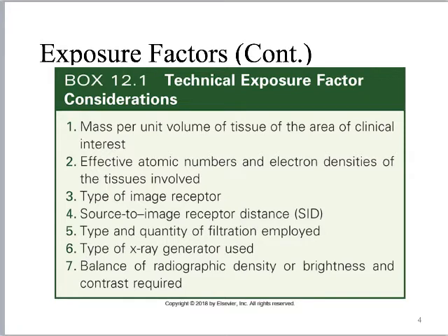There's also compensating filtration — things like a wedge-shaped filter sometimes used for feet examinations — which can also decrease patient dose. Regarding the type of generator used: older x-ray rooms with generators that fluctuated in power supply caused fluctuation in photon energy, increasing patient dose. The newest, most state-of-the-art high-frequency generator would provide decreased patient dose. Direct current devices like battery-powered portable units can also potentially yield decreased patient dose if used appropriately.